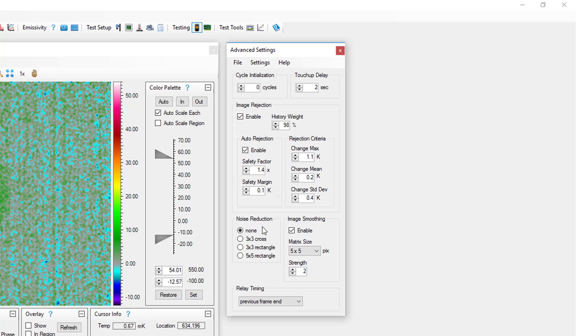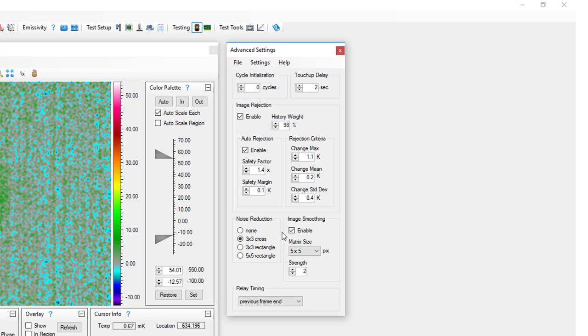Noise reduction and image smoothing help detect localized heating in lock-in images. Good starting points for these values are a noise reduction of 3x3 cross and image smoothing of 5x5 pixels and a strength of 2.